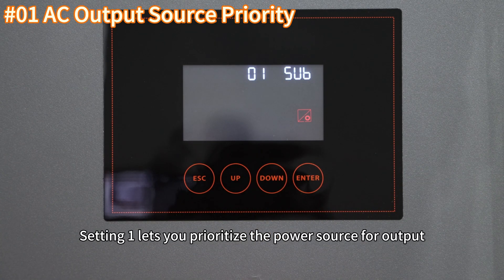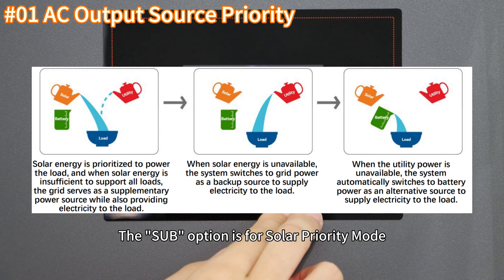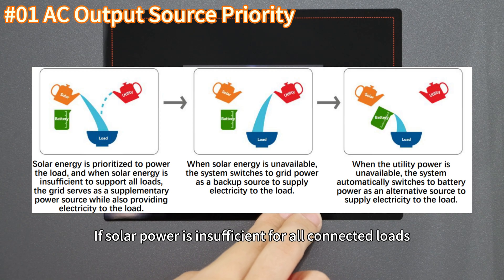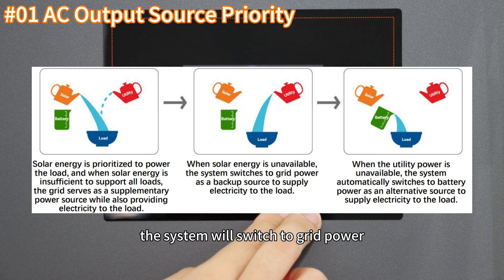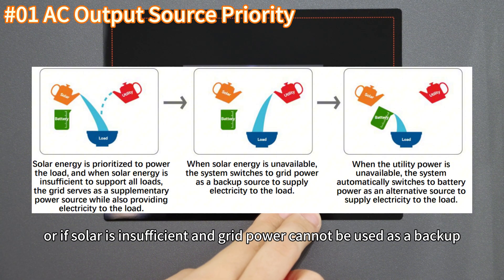Setting 1 lets you prioritize the power source for output. The SUB option is for solar priority mode, where solar power is the primary source for load supply. If solar power is insufficient for all connected loads, the system will switch to grid power, while the battery is only used if both solar and grid power are unavailable.